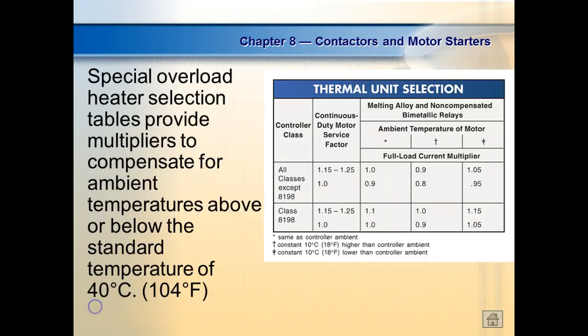Okay, guys, you'll take another test. It was 40 degrees centigrade, right? I'm saying, 104. Well, they're saying we would have to figure this out. It says higher than the controller ambient temperature. So that means if I'm running my heater, I've got a heater inside that thing that depends on a certain amount of heat to break that thing loose. If I've already got 44 degrees centigrade, that means my motor is not going to be able to raise it as much before it breaks loose, right? Does that make sense?